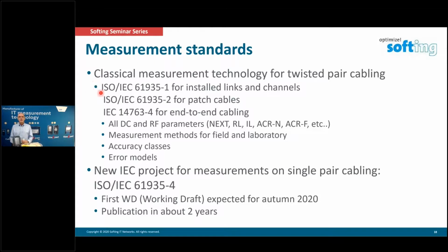This standard is very extensive, 120 some pages. However, it has one shortfall - it doesn't cover single pair. So what ISO IEC is actually starting right now is a new measurement project for single pair Ethernet, the 61935-4. There's a first working draft at the moment in preparation, and we expect to issue this as a new work item proposal to IEC in autumn, probably November this year.